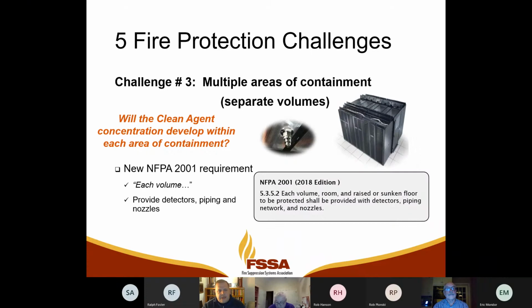And this is actually somewhat controversial. NFPA 2001 says that each volume, room, and raised or sunken floor to be protected shall be protected with 3 things: detectors, piping network, and nozzles. Detectors, piping, and nozzles. Well, aisle containment systems make new volumes inside the larger protected space. So basically, what do you need? Every time you have a cold aisle system, you need detectors, piping, and nozzles inside of it. That's a big challenge in a lot of situations, and it can increase the cost of the installation, but yet the code says that.